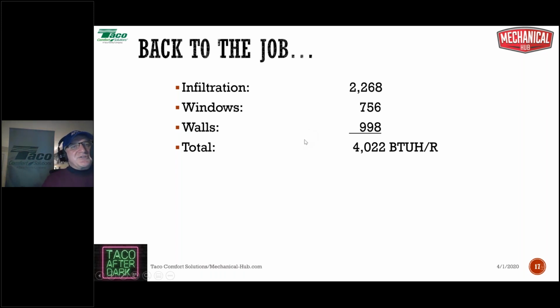It's the same thing when sizing a circulator. If your flow and head requirement is just a wee bit above a fixed pump curve, would that pump be okay? Yeah, probably just fine. Because again, we have exaggerated the heat load here just a little by math, by estimating, and that's just the way it goes. Now let's quickly do the rest of the house.